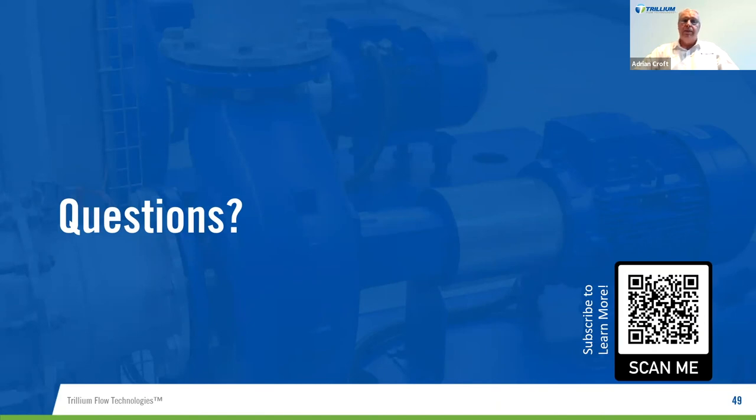I can't go into too much detail, but essentially the valves were specifically designed for safety application. They had the instruments mounted separately to the valves as a safety concern, but more importantly, they were thermally lagged by heat protection blankets. So quite an unusual application, quite unusual to wrap control systems in thermal protection blankets, but unique to the customer application and specification.